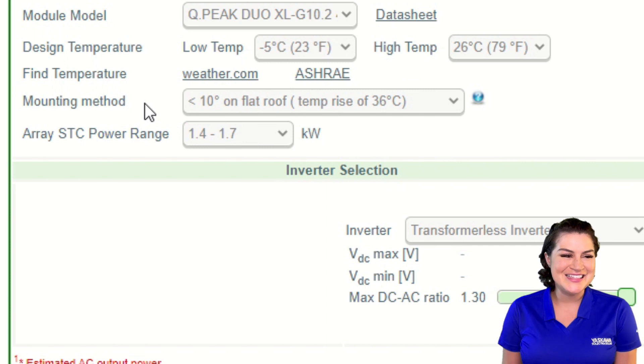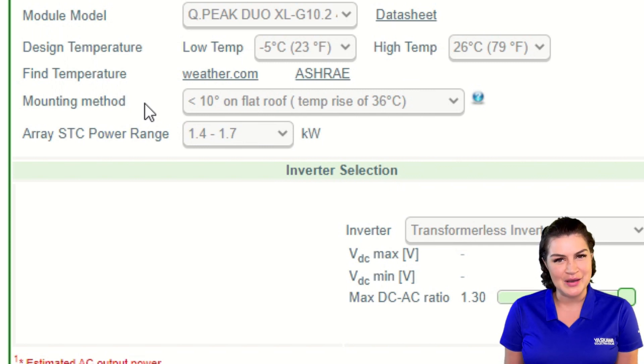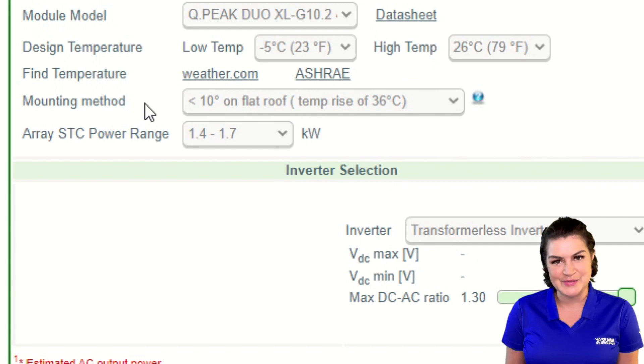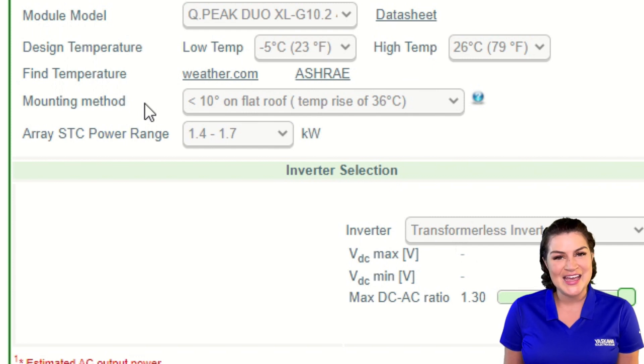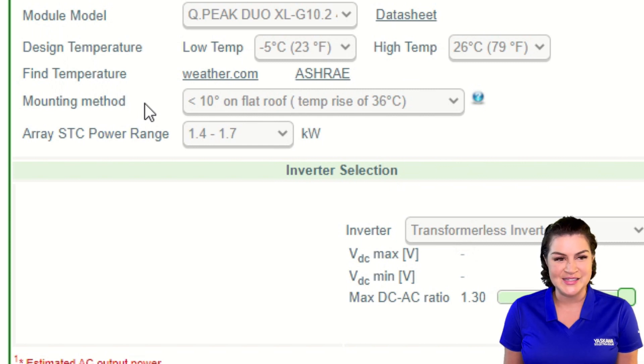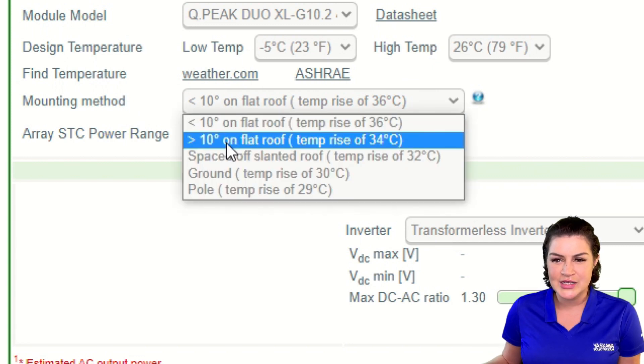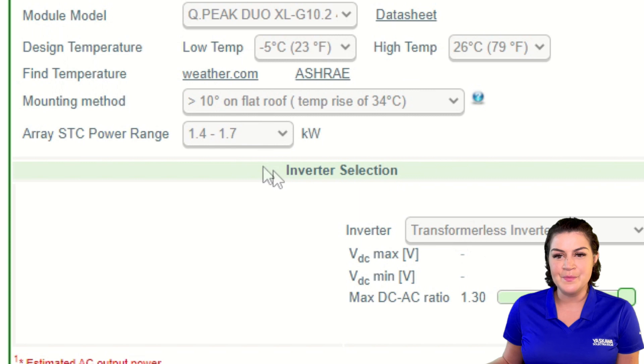Next is the mounting method. Various mounting and racking methods can result in modules experiencing a temperature rise, and this is important when determining the lower operating voltage on those warmer days.